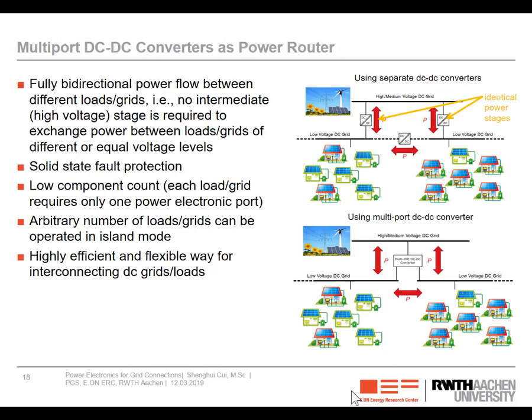And here, it's about the converter used for medium voltage DC to low voltage DC application. When we have a medium voltage DC grid, then most likely there will be DC-DC converters to connect and deliver power to different societies here and here. Then for free energy trading, we would like to install an extra DC-DC converter to interconnect these two societies. Then the problem is that if this converter is 100 kilowatt and this converter is 100 kilowatt, we would need one extra 100 kilowatt DC-DC converter. And it means higher losses, of course, and higher investment cost. So how can we address it?